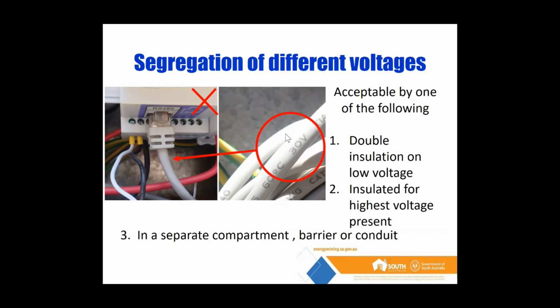So there's three different ways that you can make this compliant. What we've got here is a cable in close proximity to some single insulation, and it's only rated for 30 volts. So that's not compliant, hence the big X. The three different ways you can achieve this: first, by double insulation. If this low voltage cable in the back of this switchboard was double insulated, then we might be okay. Or this cable can be insulated for the highest voltage present. So there's a pink cable getting around. I can't mention the brand, but it is rated for the highest voltage present. Or we could have it in a separate compartment or barrier or conduit. So we could have conduit coming hard up against this RS485 label all the way back to the other Modbus connection on the other side of the appliance, and we could be okay. So that's also another possibility.